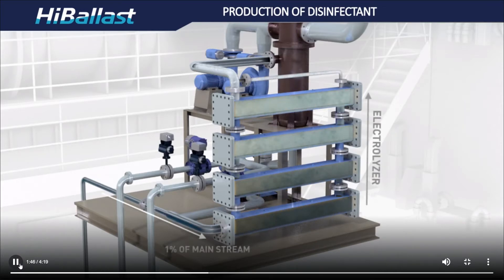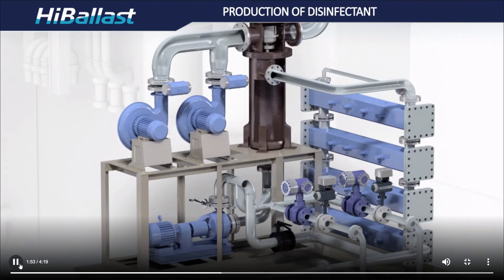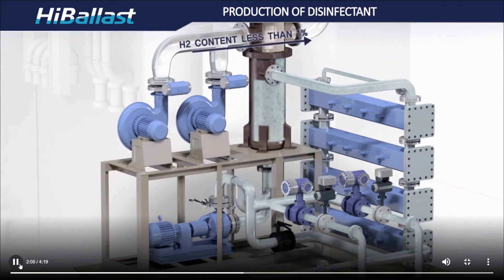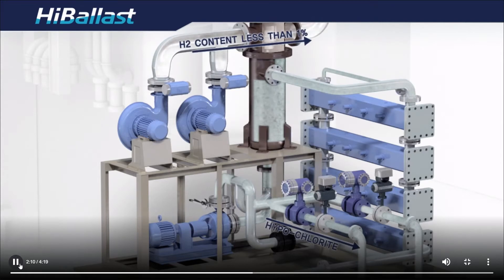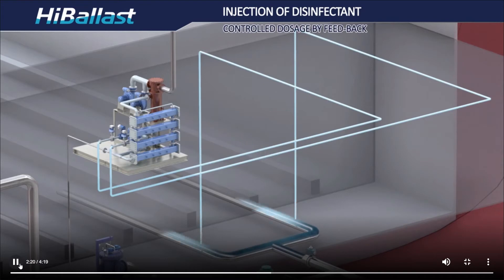To generate disinfectants, only one percent of the whole ballast water is supplied to the electrolysis unit. Sodium hypochlorite, a disinfectant, is produced in the process of electrolysis. Hydrogen gas, as a by-product, is generated, separated at a vapor-liquid separator, diluted 100 times by an air blower, and discharged forcefully to a safe area atmosphere.